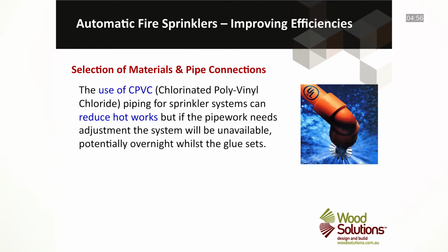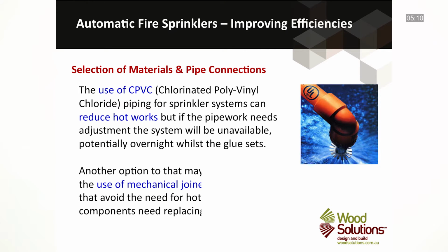Selection of materials for use on the sprinkler systems is also an important consideration. Clearly, if materials that require hot works can be excluded or reduced, then this dramatically reduces the fire risks during construction or ongoing maintenance. The use of CPVC, chlorinated polyvinyl chloride piping for sprinkler systems, can also reduce the need for hot works. However, these systems use adhesives which need time to cure. And as such, if the pipework needs adjustment, the system will be unavailable, potentially overnight whilst the glue sets. Another option that might be considered is the use of mechanical joiners for metal pipes that avoid the need for hot works if components need replacing or modifying. So as you can see, there are also a number of materials options that can be discussed with your services engineers.